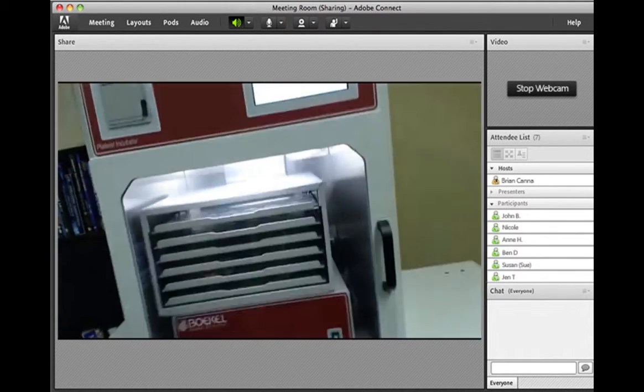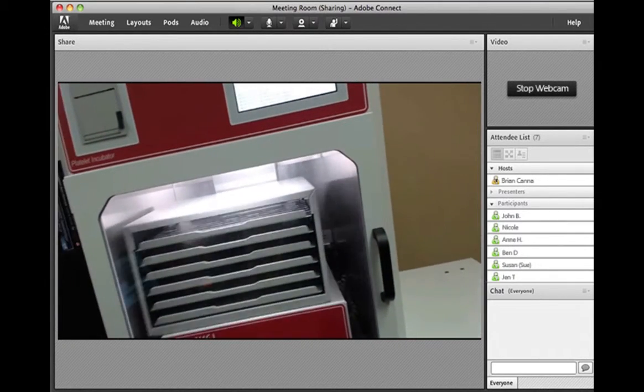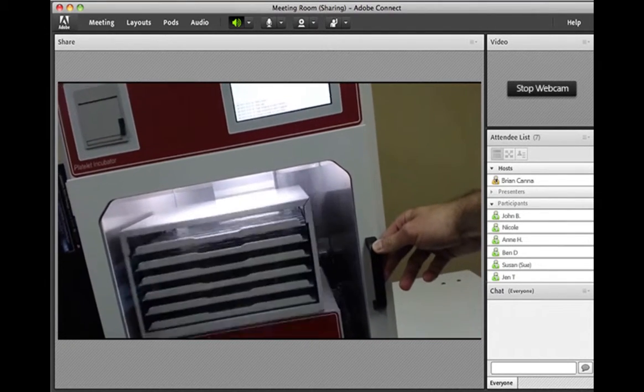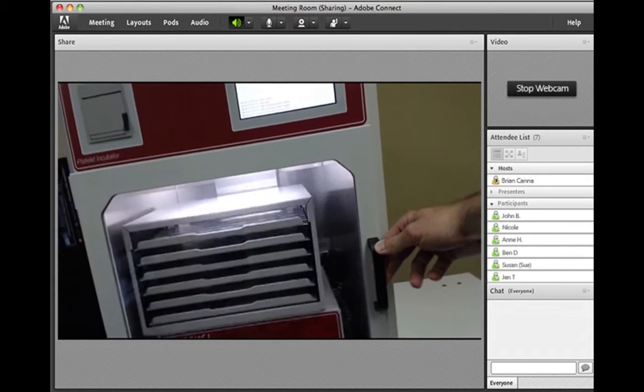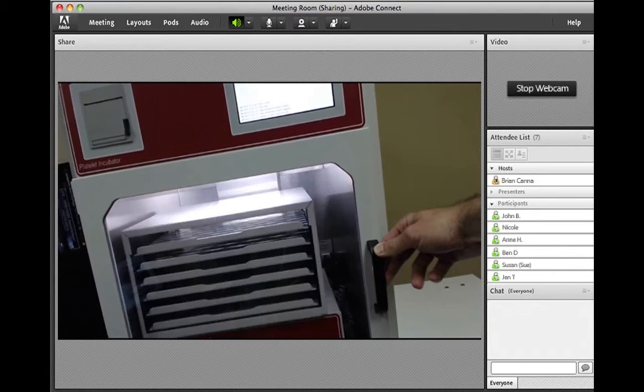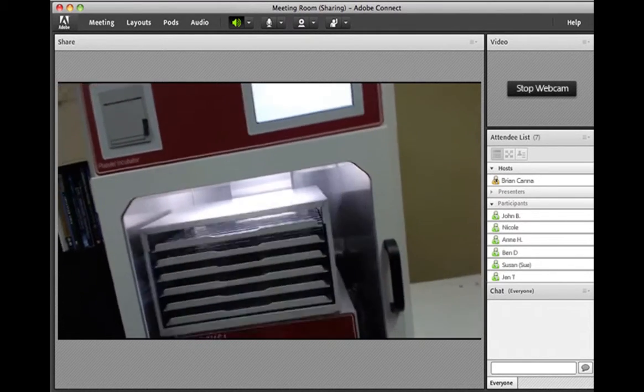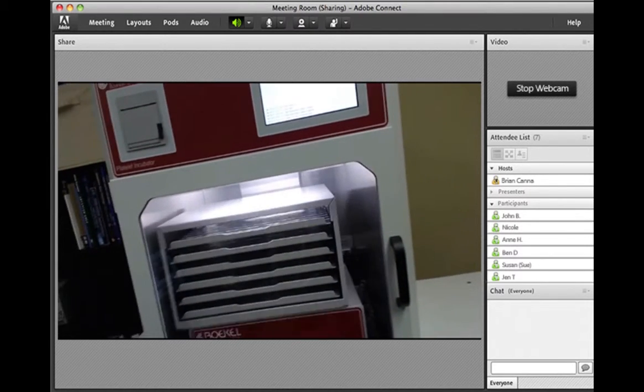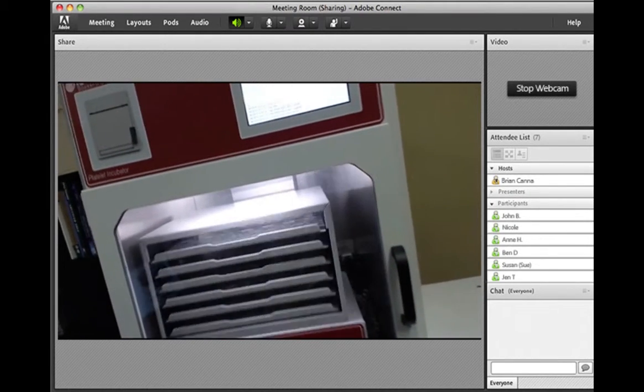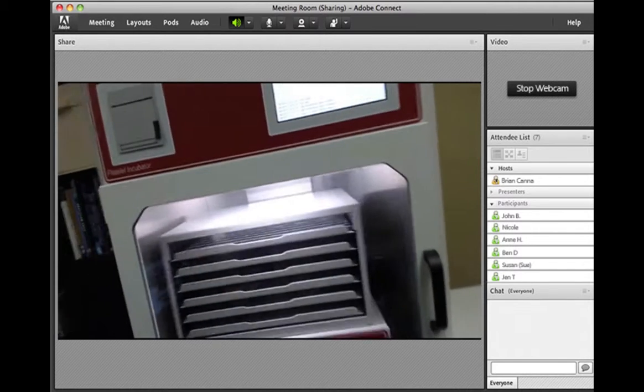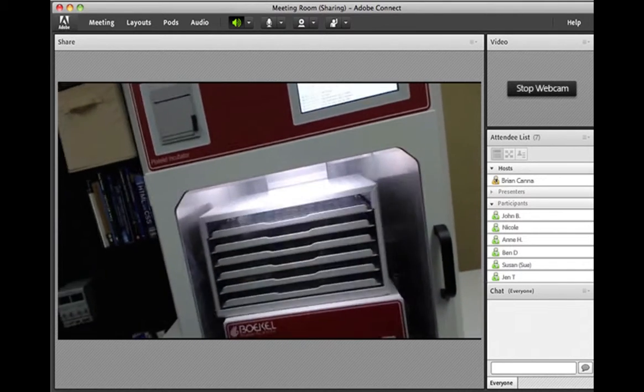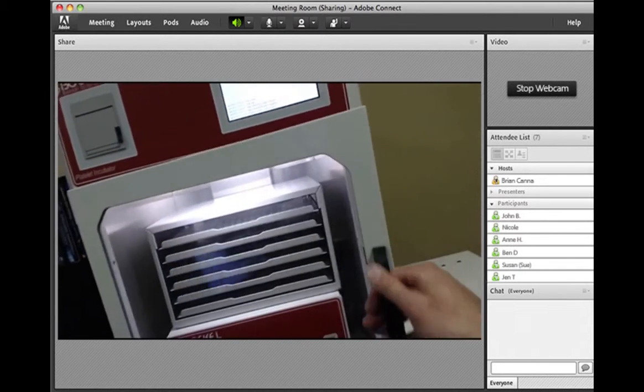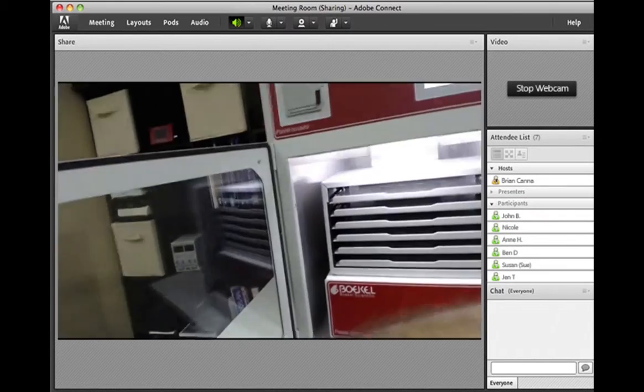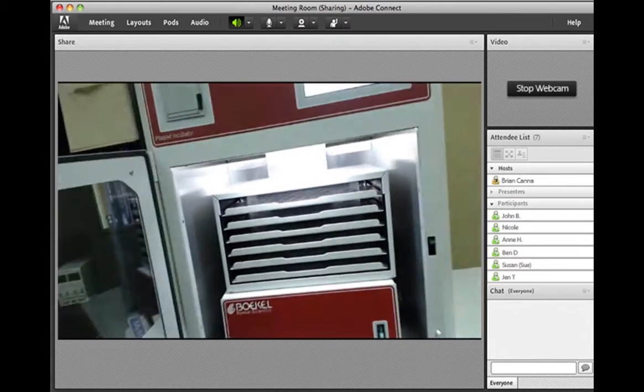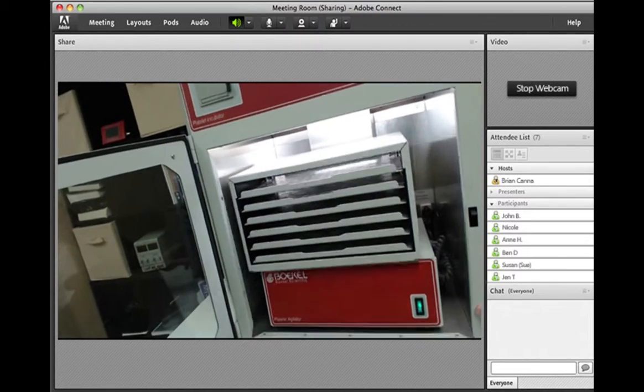Here we have our agitator. It is rotating at about 60 RPMs. It uses a dual axis agitation. We found that in dissolution studies this actually increased the mixing capability of the unit rather than going side to side. When we open the door, we can see that the agitator stops. We also have a switch in here in case you want to start the agitator back up.